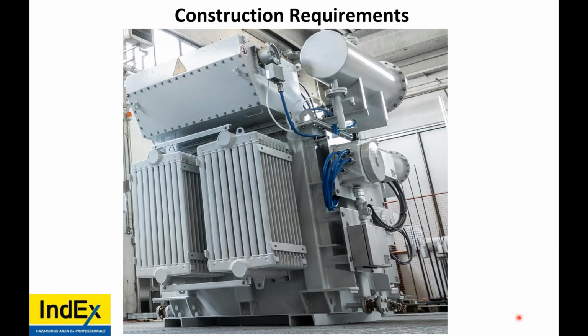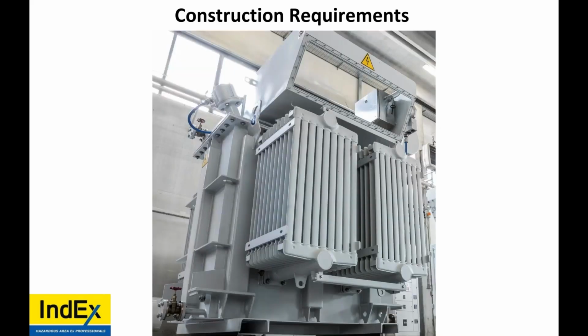So here's another example of the one that we showed you before from a view from the other side. So this one here, that could potentially be a temperature sensor or a pressure sensor on the main enclosure. Yeah, that would be an EXE enclosure where we do the terminations. So here it is when it's open. It then has another box inside. There could also be heaters up there, space heaters, EXDE space heaters. And then we have this one up here. That could be a sonic, could be an instrument for level indication, an ultrasonic, perhaps.